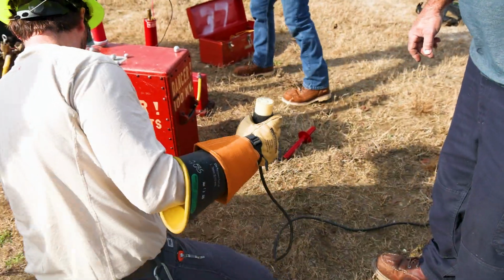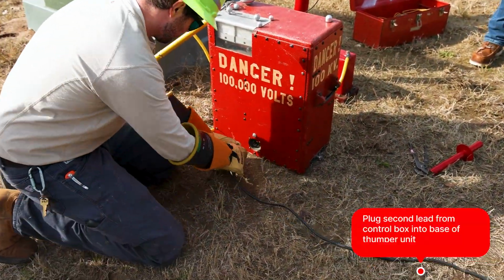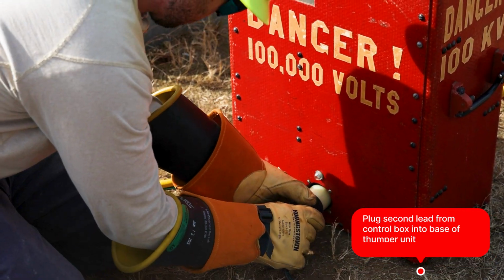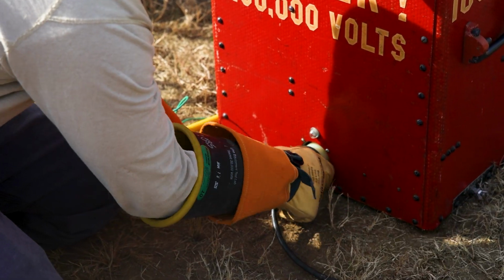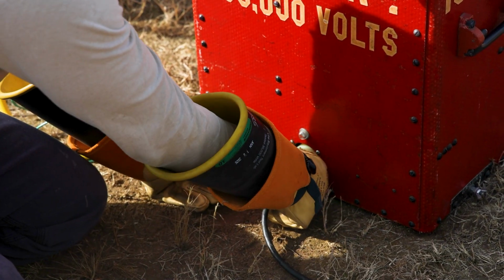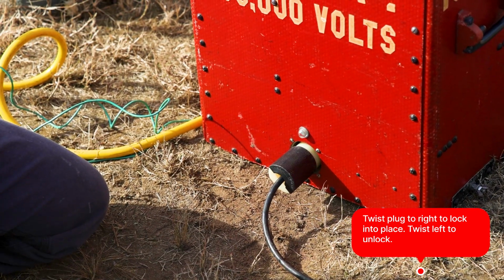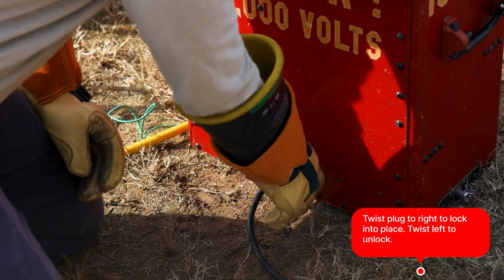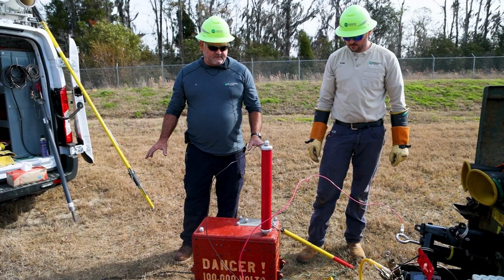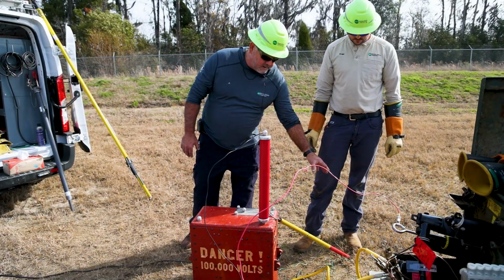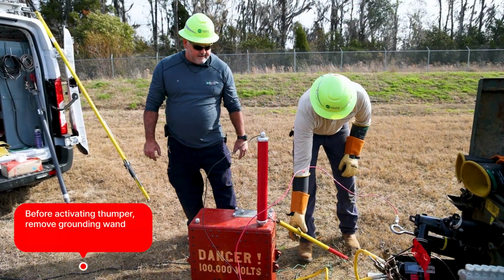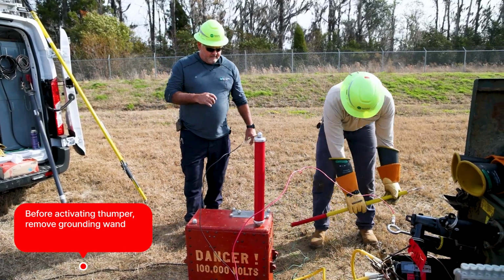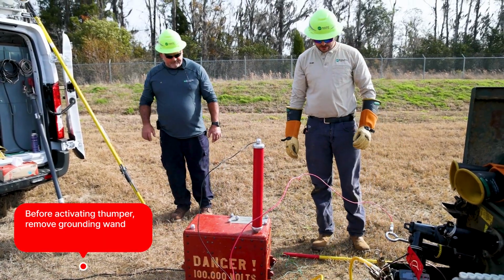This next step is to take the second lead coming out of the control box and hook it to the thumper. Once you install this connector, you have to twist it to the right to lock it in place, twist it to the left to unlock. At this point, he's ready to start thumping the cable. First thing is you need to remove your grounding wand from the top of the machine. You can lay it on the ground out of the way.